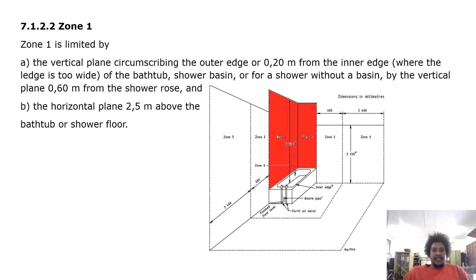Zone 1 is the vertical plane circumscribing the outer edge — or 0.2 meter from the inner edge where the ledge is too wide — of the bathtub, shower basin, or for a shower without a basin, by the vertical plane 0.6 meter from the shower rose, and the horizontal plane 2.5 meters above the bathtub or shower floor. As indicated in red, that is the outside edge up to 2.5 meters above the bath, or in the case of a shower, 0.6 meter from the shower rose.